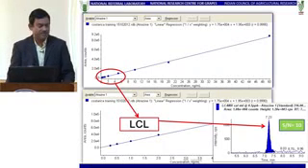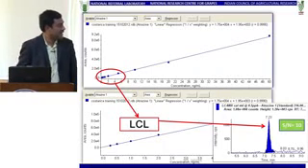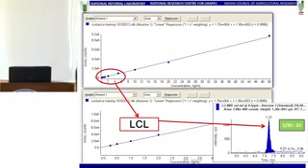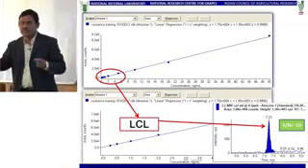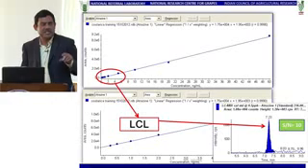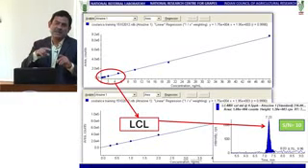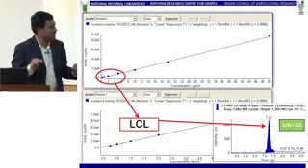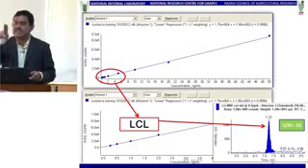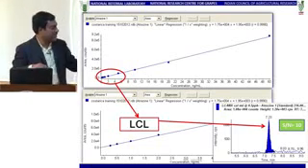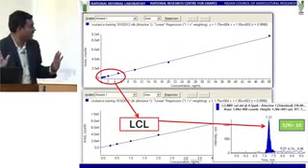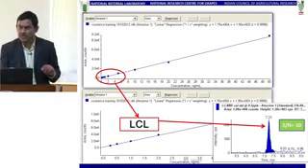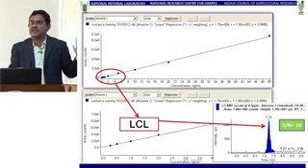If you look at this calibration line, it's a pretty good calibration. But you need to zoom into the lower part, because the lower part is where response is not so good. If you look at the peak shapes in the lower concentration levels, they are never so good. There could be a little bit of tailing, a peak may not be so sharp, all these issues come up. So at the lowest calibration level, you should look at the shape of the signal and the signal to noise ratio. For example, here S/N is almost close to 10, and that's the reason you could say this is the LOQ. But another important point is the performance of the method at that level.